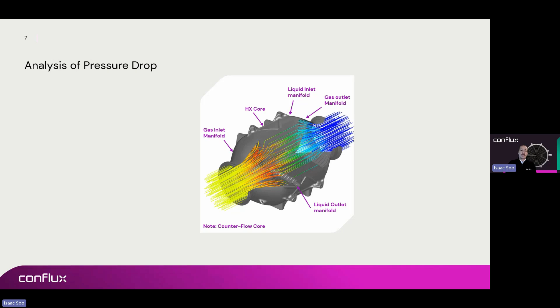The device you can see on the screen here is a counterflow orientation, meaning the fluids flow against each other, which maximizes performance. Most of the pressure contribution comes from the core region of our device, where you get really high fluid interaction with the walls, the most blocked flow path. This really contributes the most to our pressure drop in our devices.